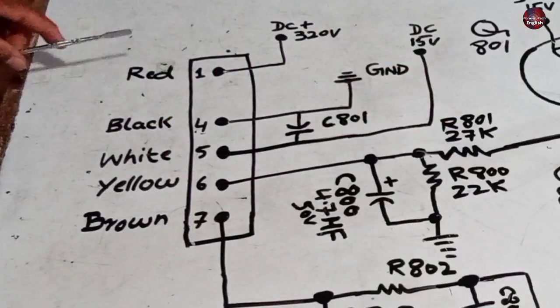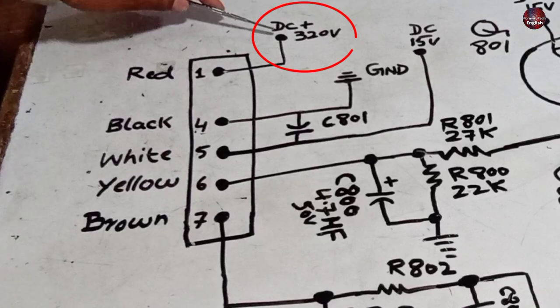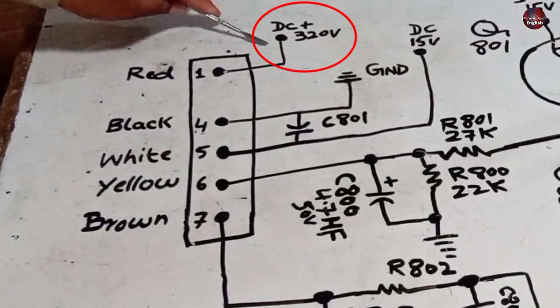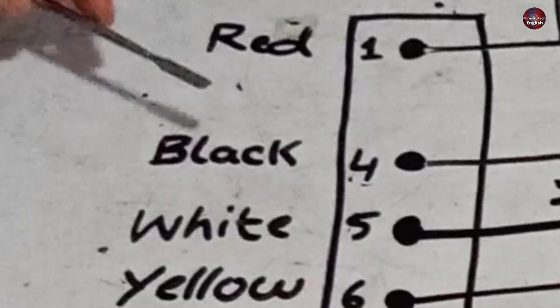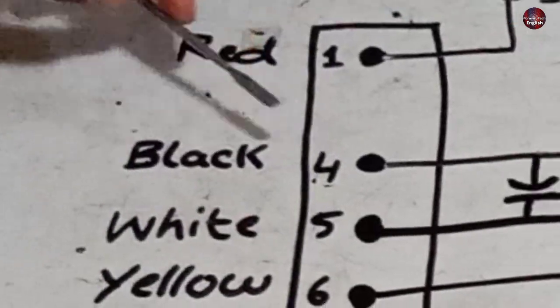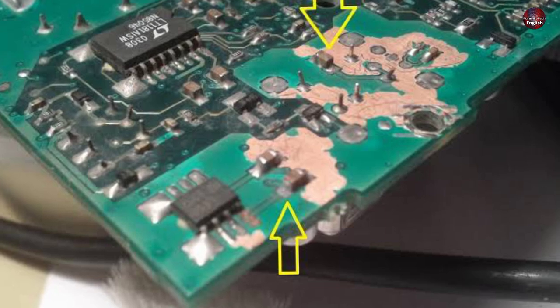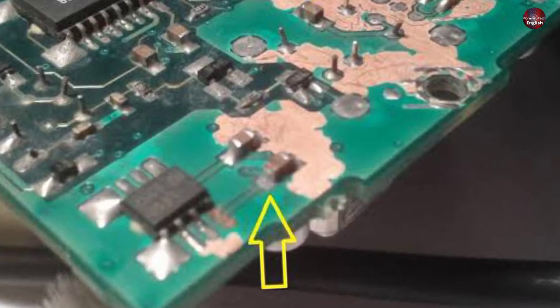This red and the first number pin should contain 320 DC volts, and the fan will work properly. Otherwise, it will not work. As you can see, the black and the 4 number pin is directly grounded, but if, due to some reason, the ground wire is missing, still the motor will not work.